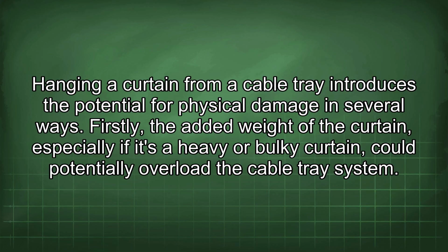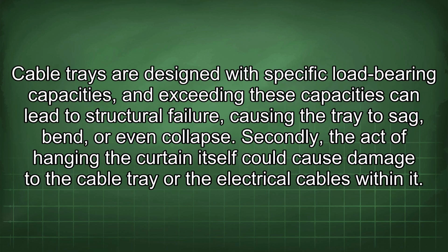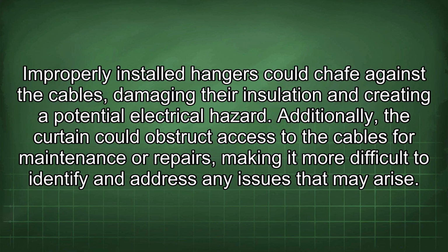Firstly, the added weight of the curtain, especially if it's a heavy or bulky curtain, could potentially overload the cable tray system. Cable trays are designed with specific load-bearing capacities, and exceeding these capacities can lead to structural failure, causing the tray to sag, bend, or even collapse. Secondly, the act of hanging the curtain itself could cause damage to the cable tray or the electrical cables within it. Improperly installed hangers could chafe against the cables, damaging their insulation and creating a potential electrical hazard. Additionally, the curtain could obstruct access to the cables for maintenance or repairs, making it more difficult to identify and address any issues that may arise.